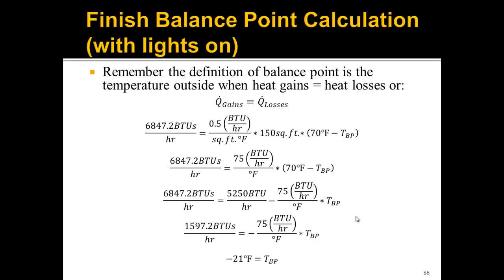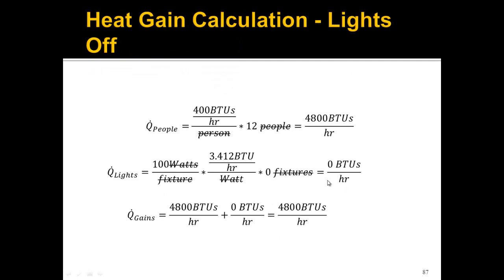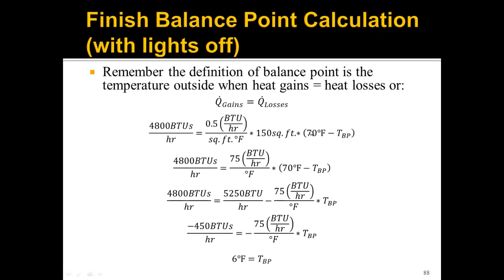That's a little surprising, so let's do the lights-off example. With lights off, there are zero BTU per hour from light fixtures, leaving only 4,800 BTU per hour from the people. Running the same math with 4,800 on the left-hand side, we get a balance point temperature of 6°F.